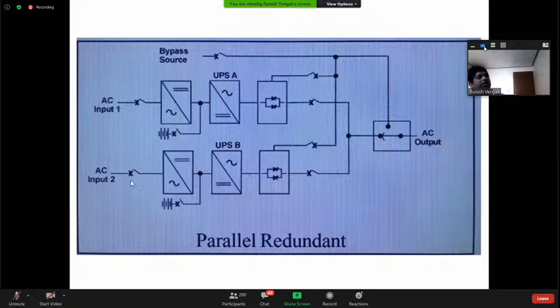If you don't want to use all these things and you want to maintain this system, and you want to go for maintenance on the whole system, you have this source - meaning you have 4 sources to supply the load. That means the load is very critical and you don't want to lose it. If you go for this scheme, even if you have a complete loss of one unit, you still have a backup here. So for reliability, you are again doubling the cost - if it is 100 and you are going for 200, that's up to you, based on reliability.